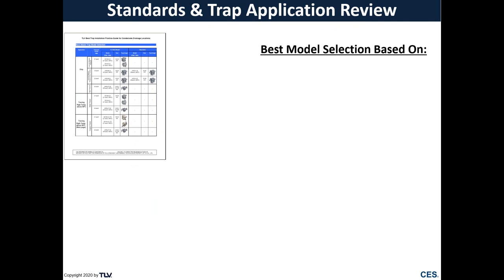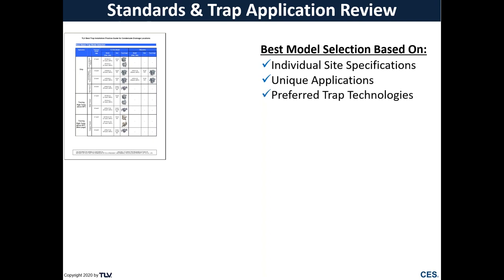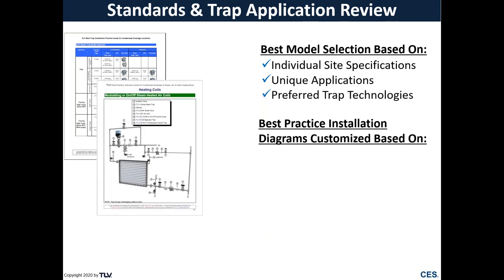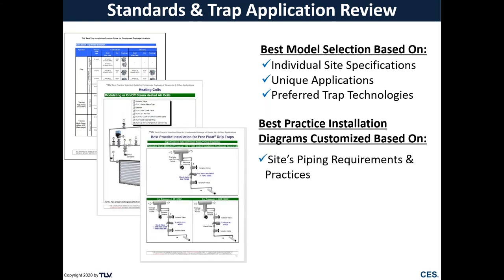We've covered a lot of different applications and a lot of different considerations. So another thing that TLV provides is what we call a standard and trap application review. Here, we will work with you to provide the best model selection for your steam system based on your individual site specifications. You may have many unique steam applications, some that we never talked about, but we can look at those and come up with best practice solutions for those as well, taking into account your preferred trap technologies. From that, we develop and provide you with best practice installation diagrams based on your site's piping requirements and practices for all of these different types of applications. This is basically to take the guesswork out of steam trap selection and sizing and make it simple and easy for you to install those steam traps and optimize your steam system.